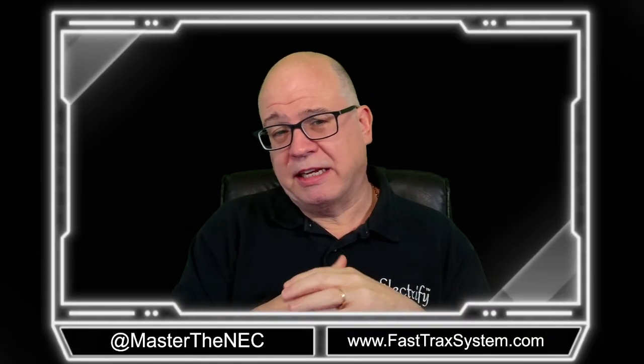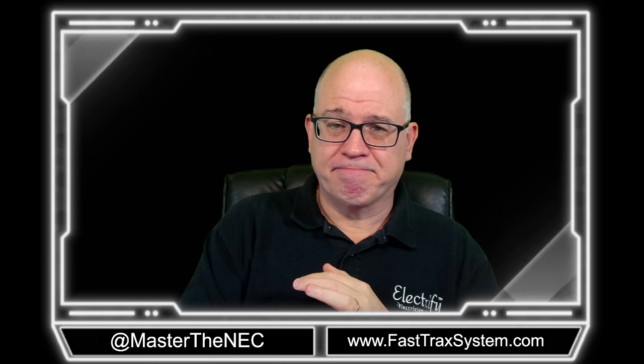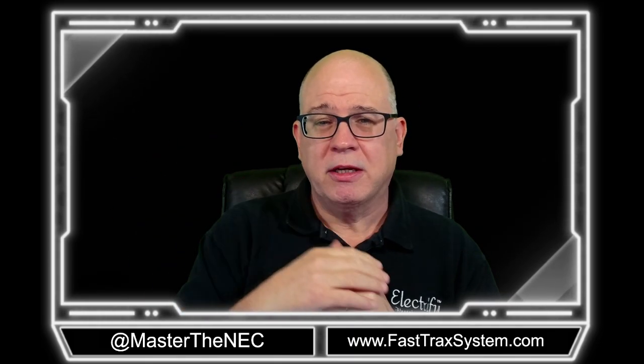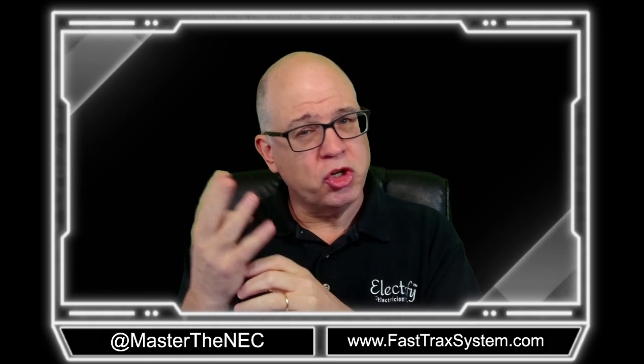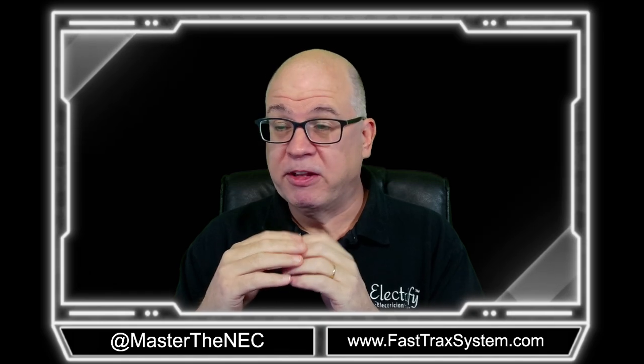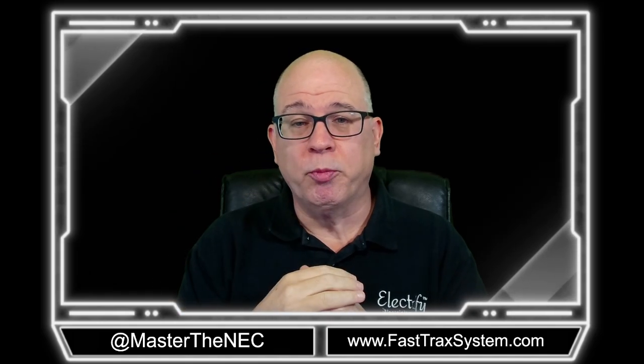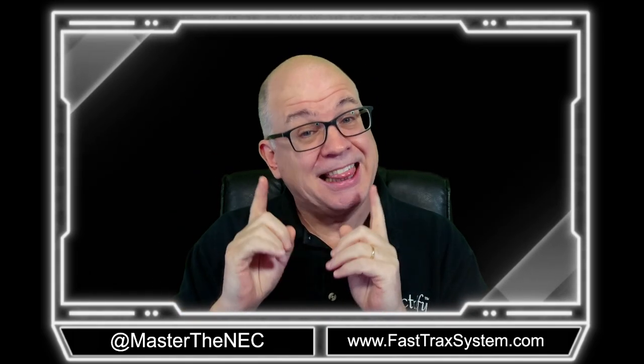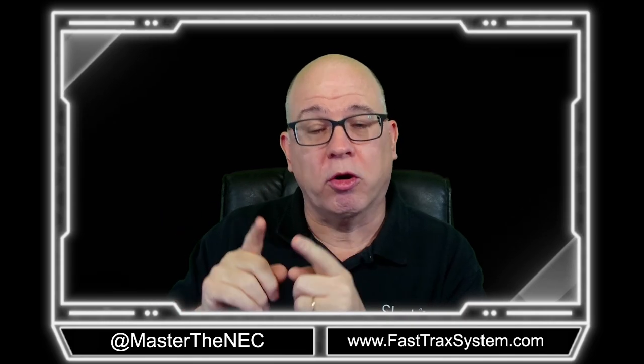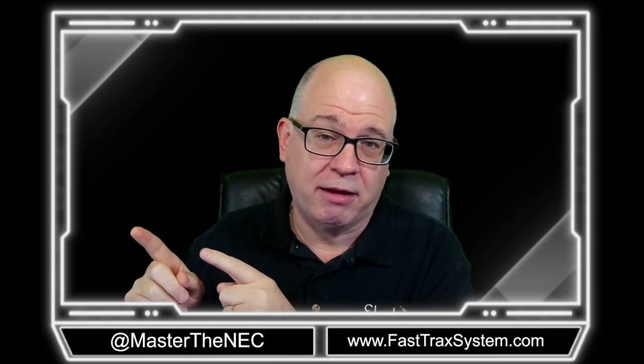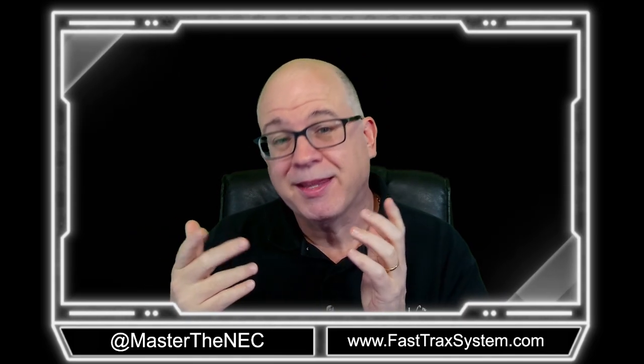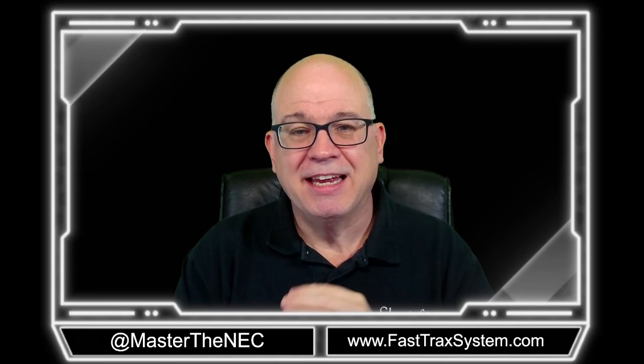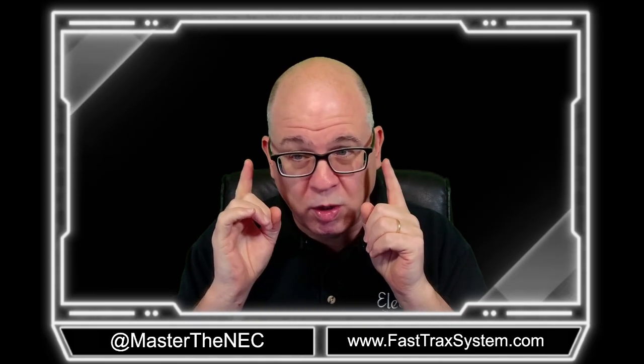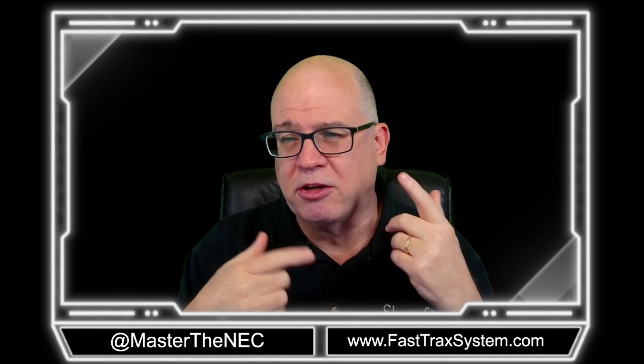So on an electrical exam, you could get a question like that. If they give you 6, then remember, up to 4, it's 2 cubic inches if it's 14. If it's 12 gauge, up to 4, it'd be 2.25 cubic inches. Then you're going to be dealing with a quarter volume for each additional equipment ground that is over 4. Pretty straightforward, right? Hopefully you got something out of this, and we will get you in the next subdivision as we continue this journey.